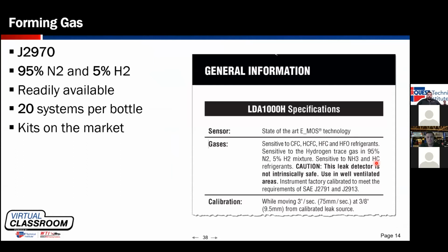The standard for it is J2970. Basically, what we're doing is we're taking a piece of equipment, we're using a gas that is 95% nitrogen and 5% hydrogen, pressurizing the system with that, and then using a leak detector that is capable of detecting the hydrogen to do a leak test. I did check, forming gas is available from some gas supply houses. Air Gas has it available. My local Air Gas does not stock it, but they said if I wanted a bottle, I could get it in a couple of days. They claim 20 systems per bottle of forming gas can be detected.